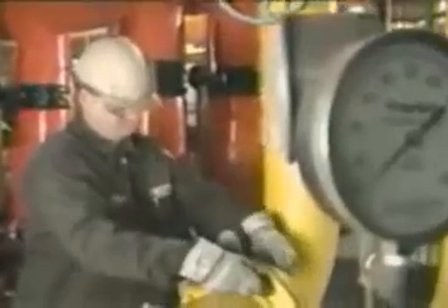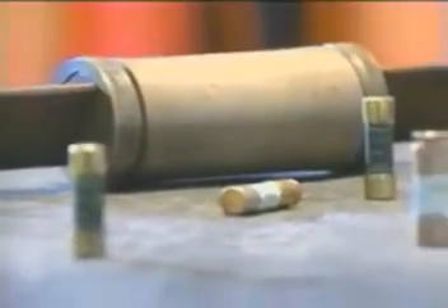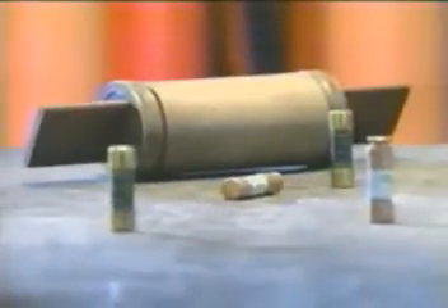This step goes beyond simply turning the power off. Step 3 involves carefully isolating the system from every energy source feeding it. Close valves, throw main disconnects, throw circuit breakers. Don't forget to disconnect or cap any auxiliary power sources too, such as secondary electrical, steam, hydraulic, or pneumatic systems. Don't shortcut this step by simply pulling fuses. They are too easily replaced.